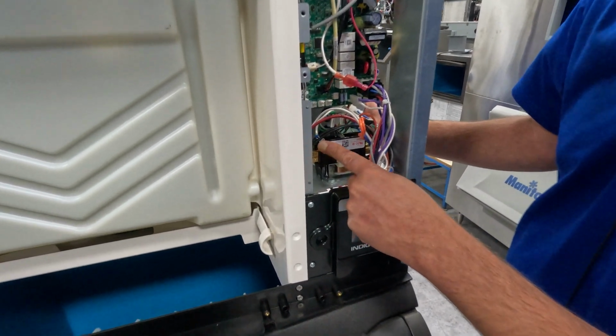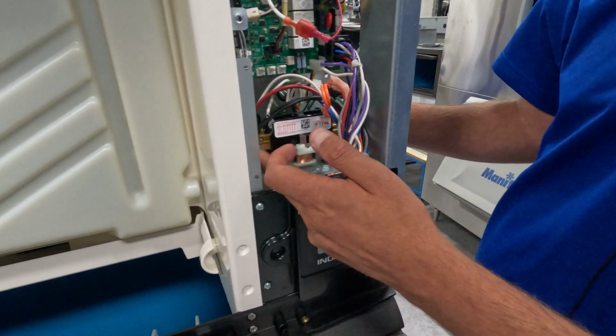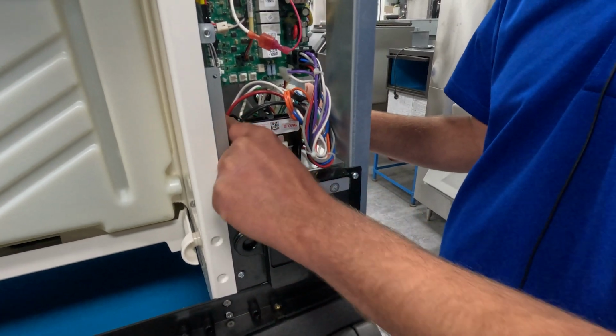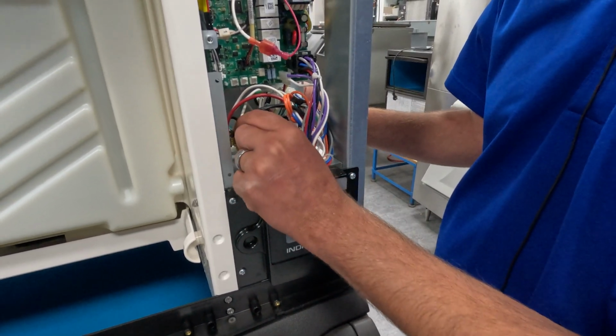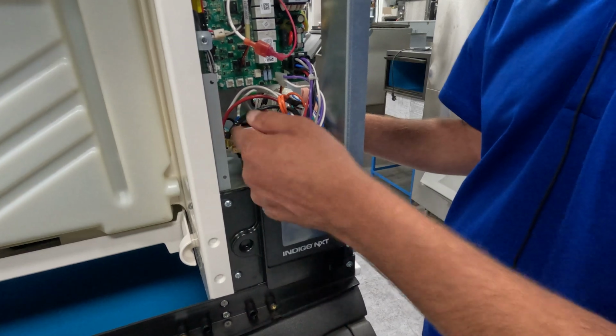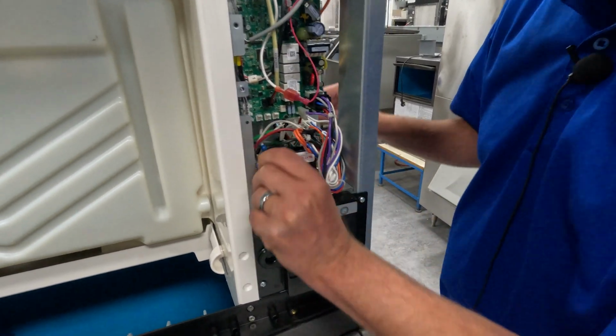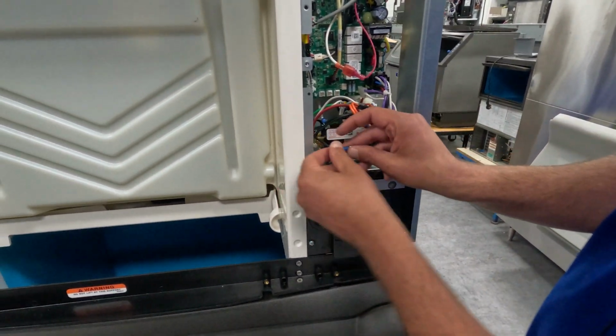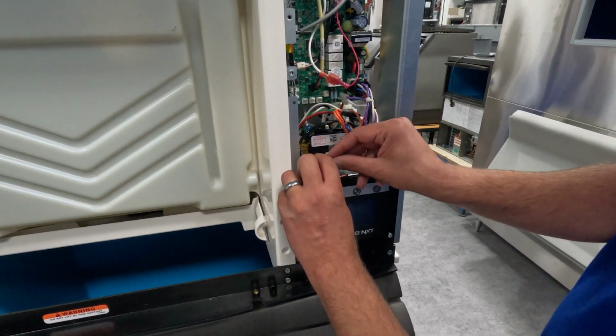We're going to need to wire this all to the line side of the contactor, that's going to be here. I'm going to match my black wire with the black L1 and my white wire with the white L2 on my contactor. Try to make sure we get a good look in here, at least on the black wire you will.